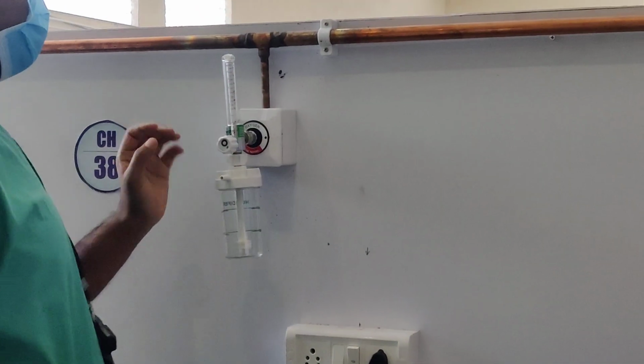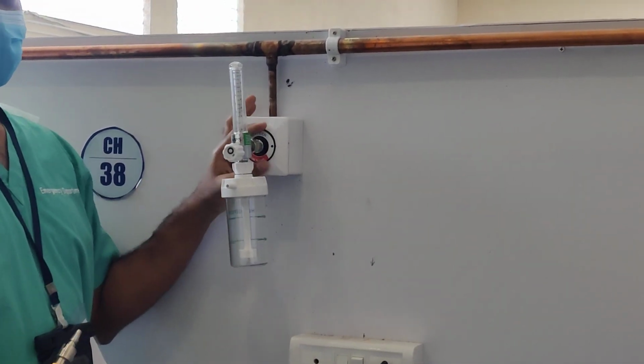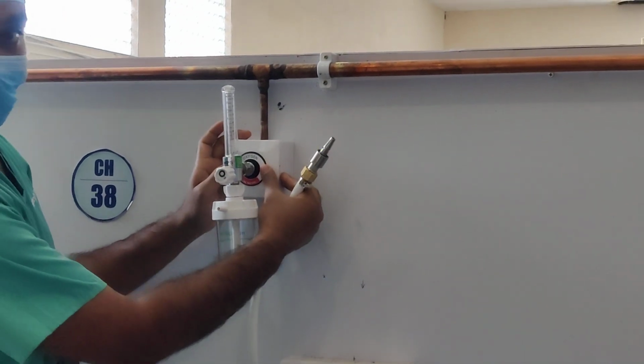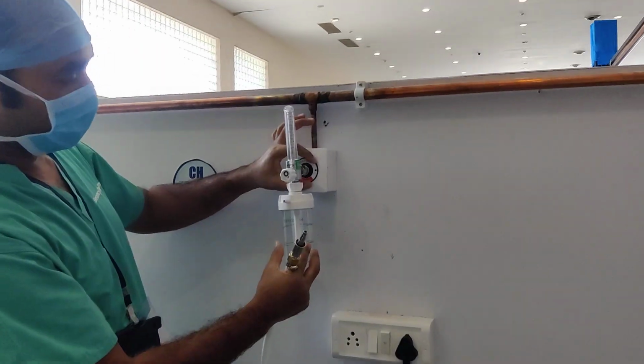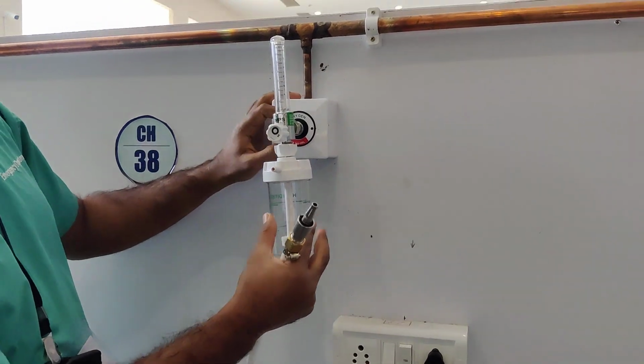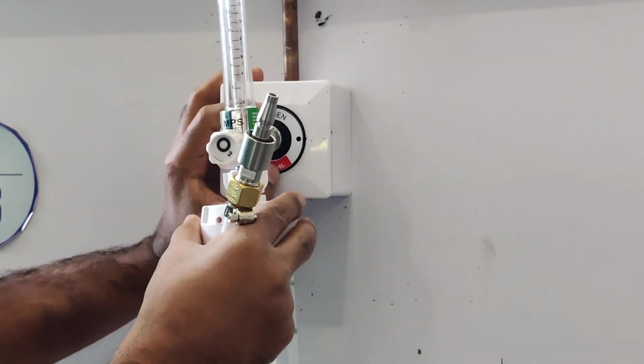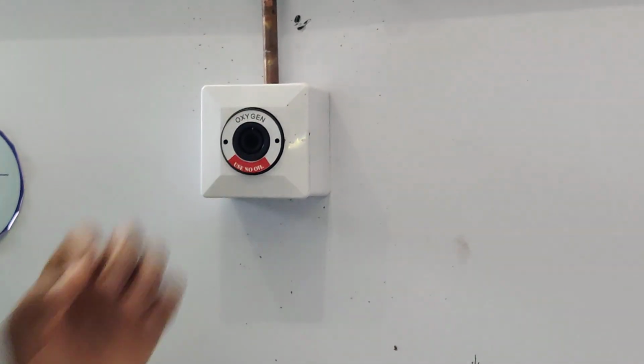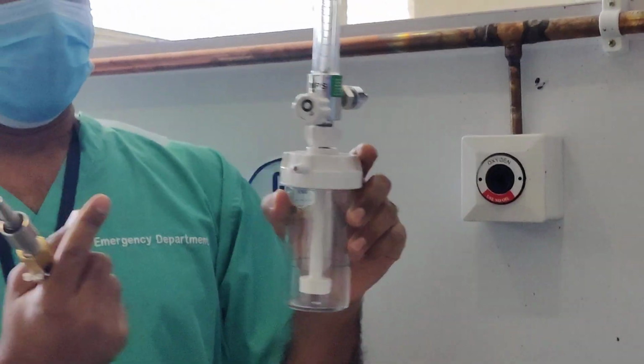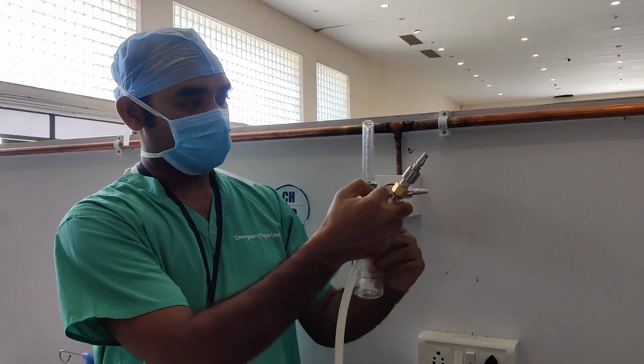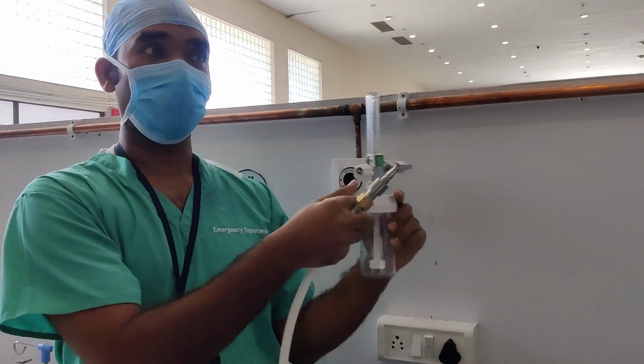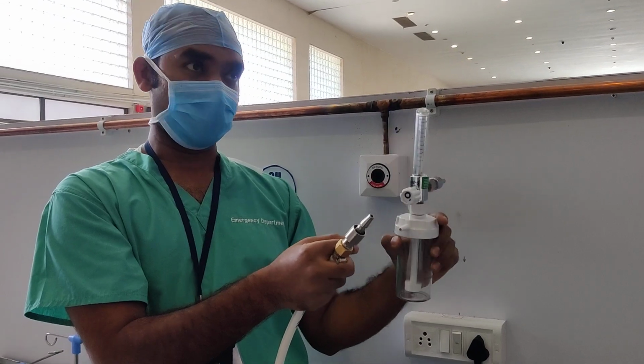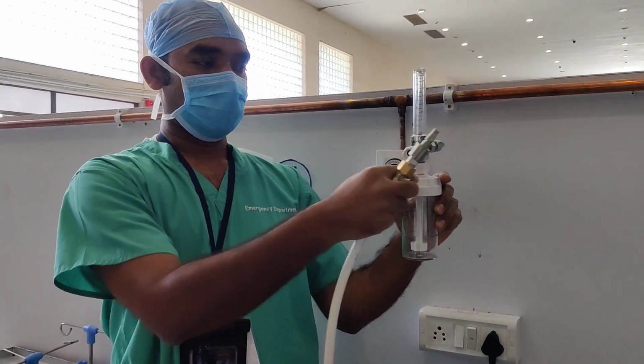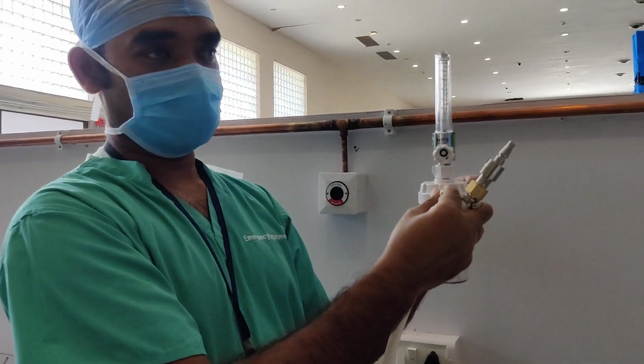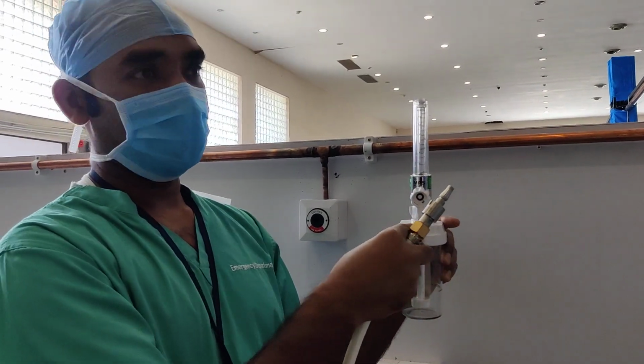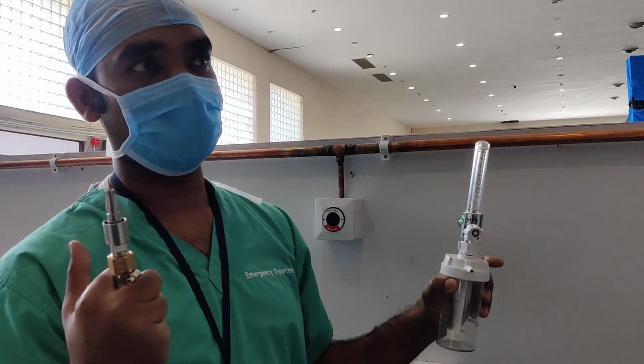Usually some form of flow meter is connected to the wall. So what you need to do, just come a bit closer. There is a circular ring here on the wall on this connector. You need to press it, then this flow meter will come out easily. This is a flow meter. Through this flow meter, you can give your oxygen from 1 liter to 15 liters. So when you are using a nasal cannula, face mask or non-rebreathing mask, use this flow meter. And this is an outlet to give oxygen. You can connect your tubing here, and another end of this oxygen tubing will go to the patient end.